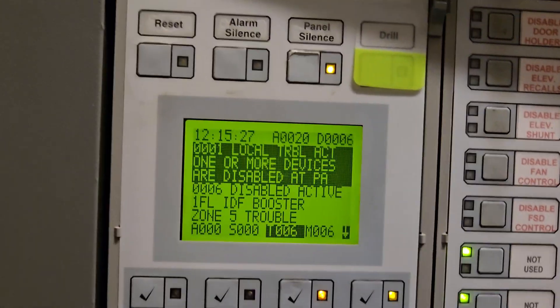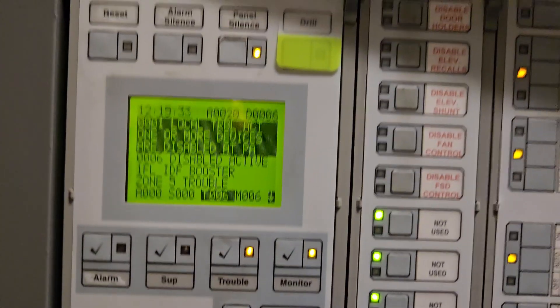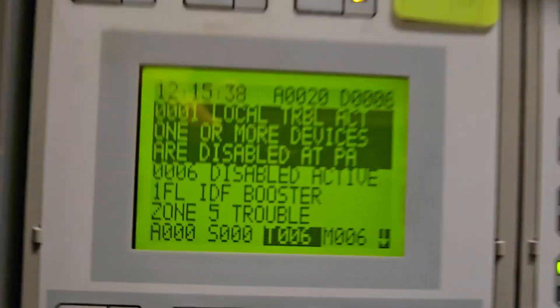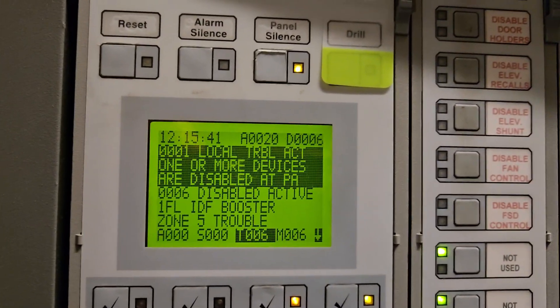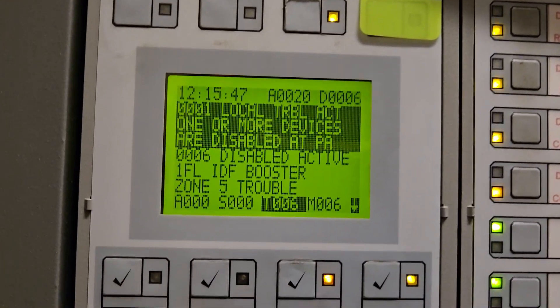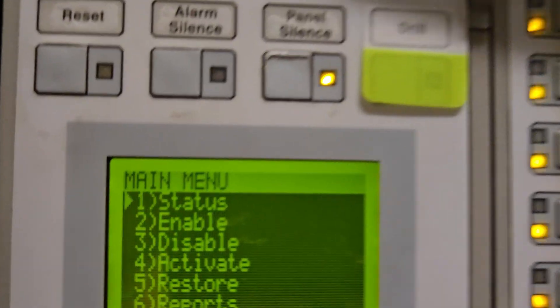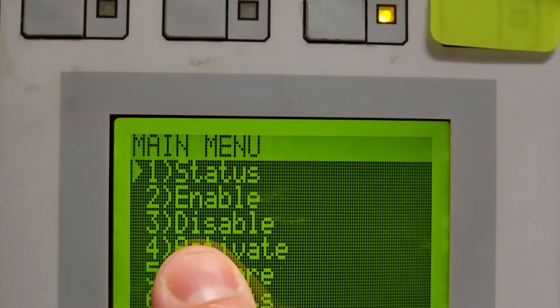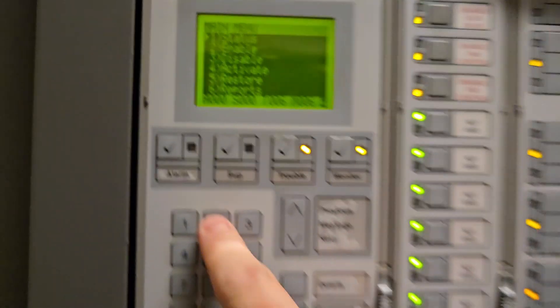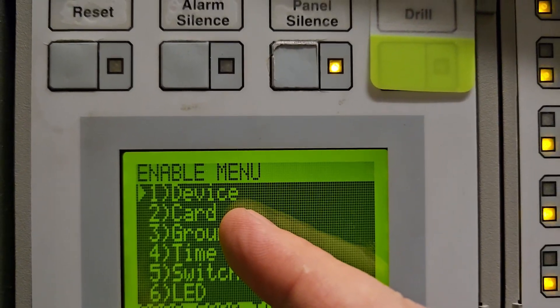Now the first floor audible circuit is disabled. If I were to sound the alarm, the other floors would go off in the building but not the first floor because I have it disabled. Now if I wanted to go back and enable those points — because I want to test the first floor — I need to enable those points. So I'm going to go back to my command menu, and this time instead of going to number three for disable, I'm going to go to number two, which is enable.